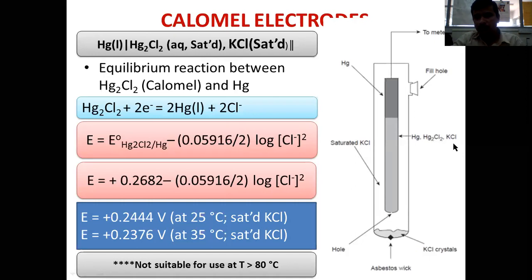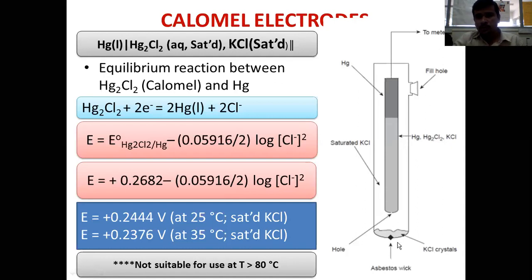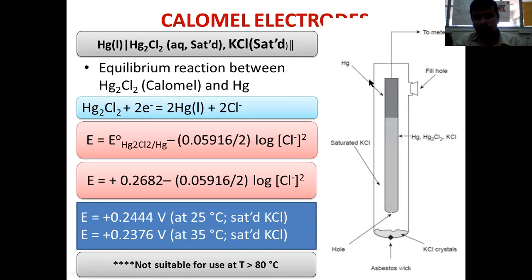In the internal tube, you fill mercury, mercurous chloride, and saturated KCl. The lower portion contains mercury, mercurous chloride, and KCl, while the upper portion contains elemental mercury. Mercury acts as the metal electrode and is connected to the potentiometer by means of an aluminium or platinum wire. There is a frit made of asbestos that acts as a salt bridge, providing interconnection between the external solution and the solution inside the electrode.